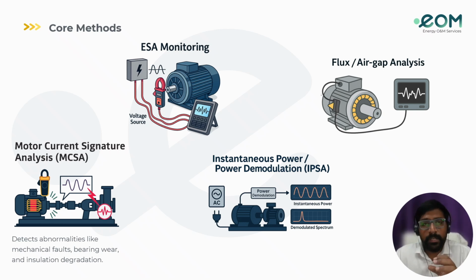So as we see, MCSA, motor current signature analysis, is your workhorse, and ESA tells you when the supply is the culprit. IPSA, instantaneous power demodulation, makes mechanical torque problems obvious, and flux is the gold standard where you can get near the end winding. Use these methods for critical assets, and trend the features with dB or percentage slip. That shows ESA moving from snapshots to predictive decisions as well.